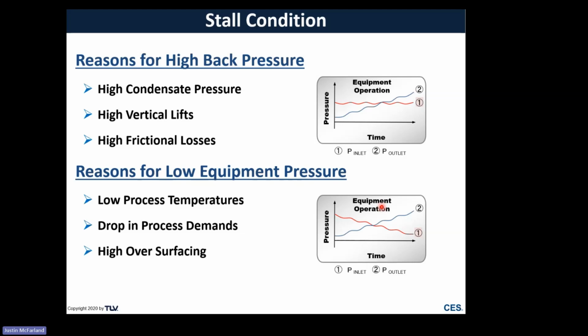that means that process heater has a lot more heating capability than we need. So in order to compensate, that heat exchanger is going to throttle its LMTD, throttle its BTU delivery, and reduce the pressure to the steam, and end up potentially with a negative differential scenario.